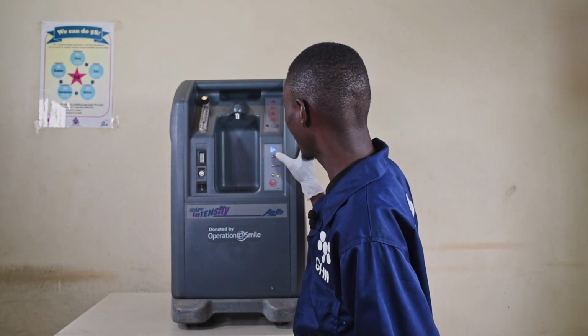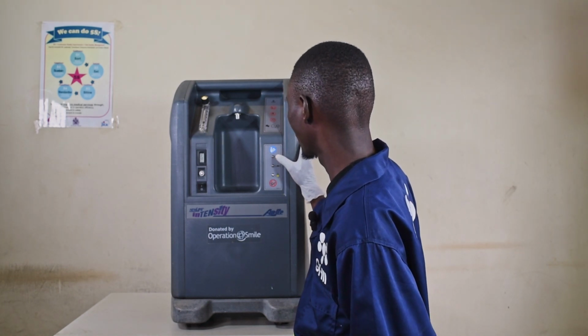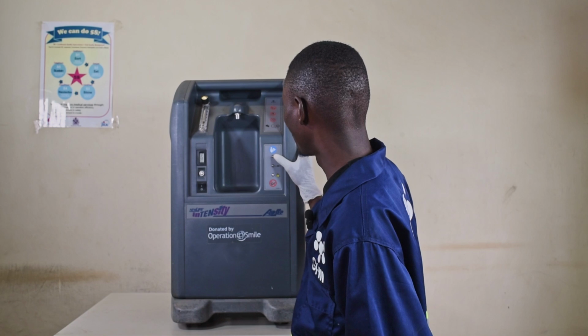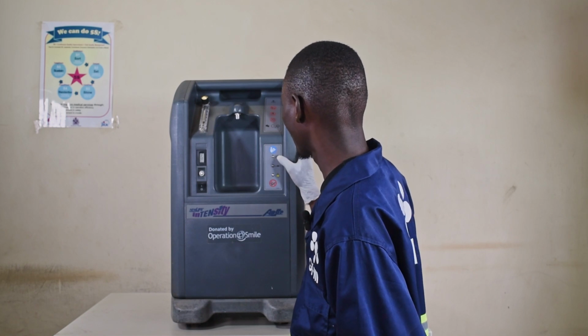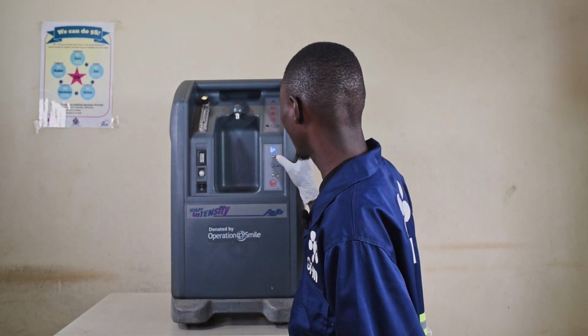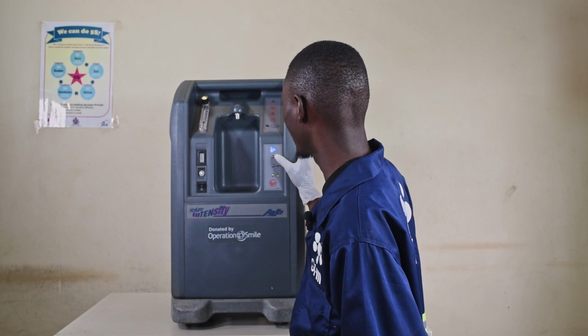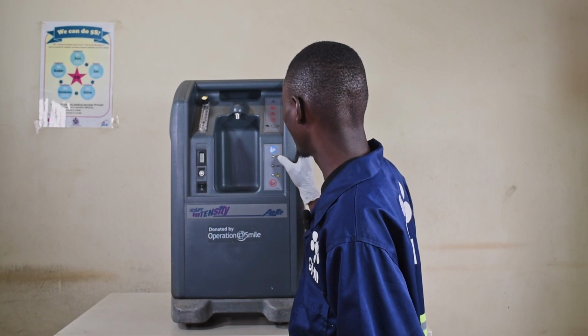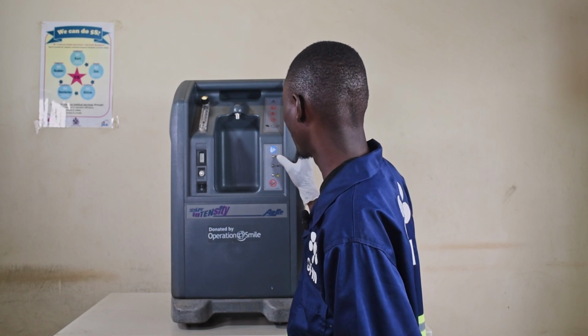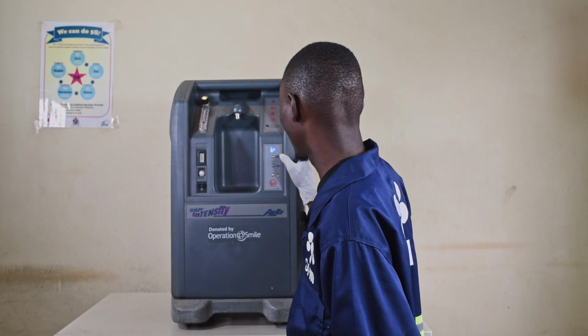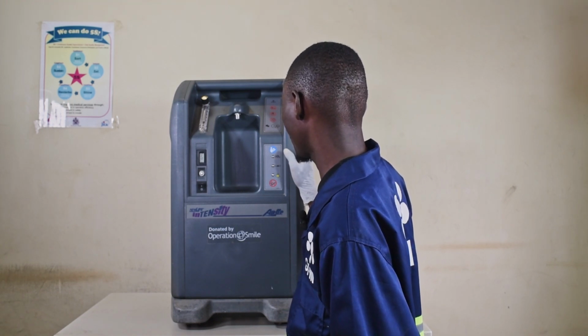The top indicator is for oxygen purity. It turns yellow when the machine is just switched on. Once the oxygen concentration has stabilized, it then turns green. If the purity is below 82%, which is the recommended level, the indicator turns red and an alarm will sound.